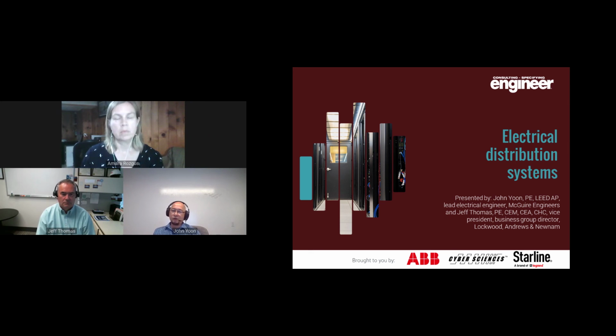So you're going to use the benefit of being able to sense current at each one of those locations and flip it on its head. While in traditional selective coordination with zone selective interlocking, instead of tripping at the breaker downstream, you're tripping the breaker at the main to clear that fault as quickly as possible. So basically, the breaker at the main sees current coming in, but the breaker downstream doesn't see the current going out. So you know by natural logical function that the fault is occurring at the main, and then you have an arc fault condition where you should trip that breaker quickly.